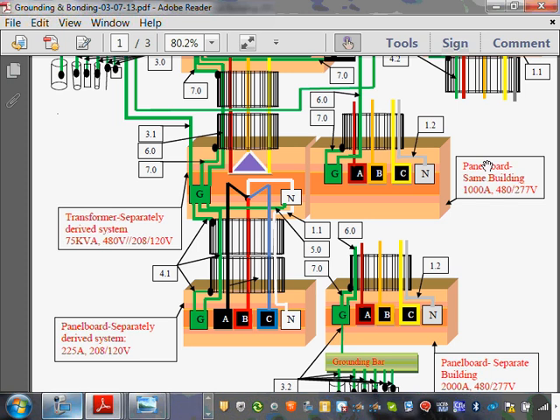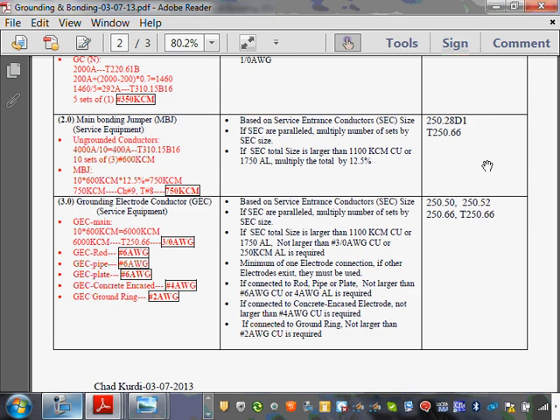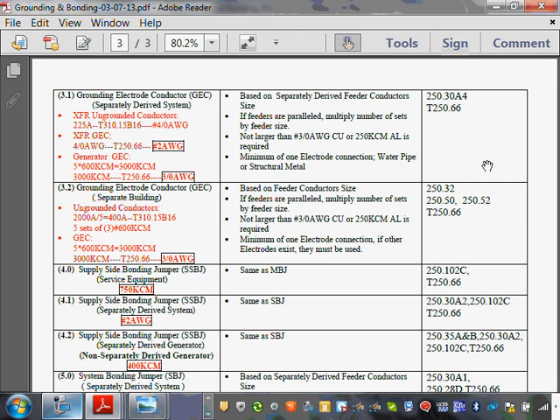Now you need to take the equipment grounding conductor. Can you guess 3.1 here? Going all the way, you need to size the grounding electrode conductor. So go to 3.1, will ya? Okay, here's my 3.1. The way we size the 3.1, guys, is based on the size of the feeders coming out of the transformer on the secondary side of a transformer. So it's called the grounding electrode conductor at the separately derived system.